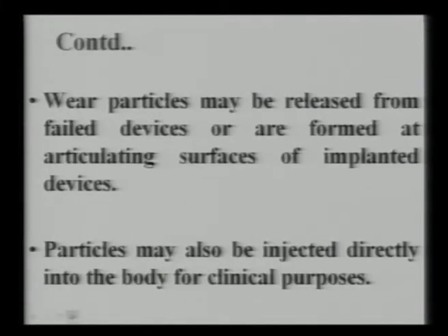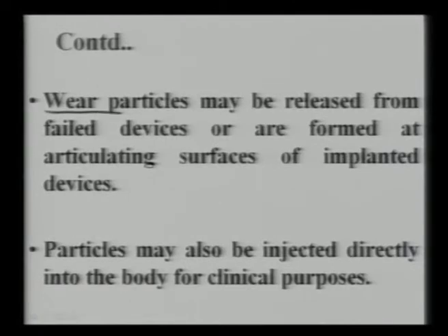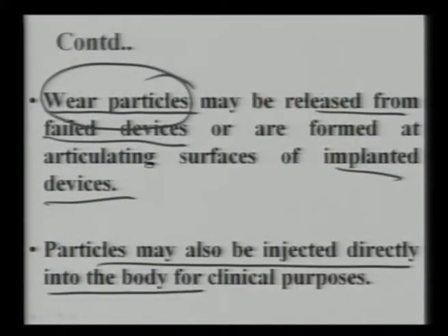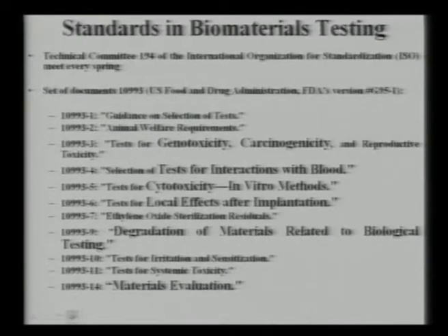Chronic toxicity often occurs because biomaterials experience corrosion and wear in the in vivo environment over long periods, generating particles. Wear particles released from failed devices form at the articulating surfaces of implanted devices and are typically micron-sized or nano-sized. Finer particles have greater toxicity — nano-sized particles have more toxic effect than micron-sized particles. Particles may also be injected directly into the body for clinical purposes.